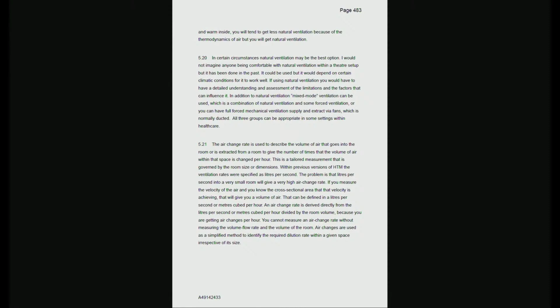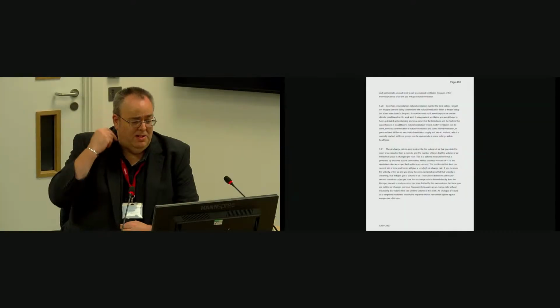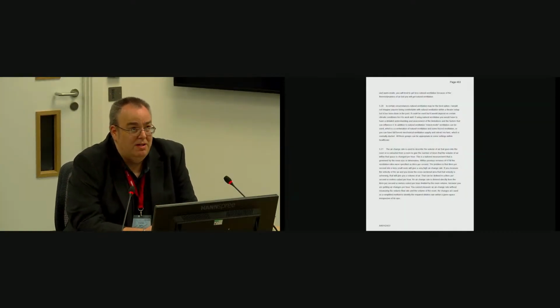You say that litres per second used to be the measure that was deployed in guidance. Is that right? Yes. And why did people decide to change it and use ACH? Because the litres per second guidance that is referenced in a SHTM 2025 relates to a standard theatre size. So at a given room size, the litres per second equated to 20 air changes an hour. However, if you build the room to a different size, it would arguably be either overventilated or, more worryingly, underventilated if you stick to a straightforward litres per second provision.